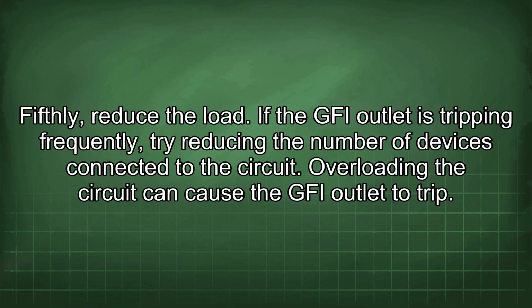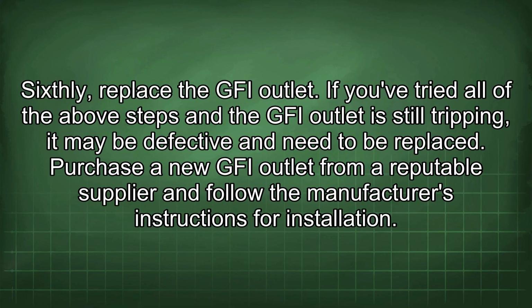Fifthly, reduce the load. If the GFI outlet is tripping frequently, try reducing the number of devices connected to the circuit. Overloading the circuit can cause the GFI outlet to trip. Sixthly, replace the GFI outlet. If you've tried all of the above steps and the GFI outlet is still tripping, it may be defective and need to be replaced. Purchase a new GFI outlet from a reputable supplier and follow the manufacturer's instructions for installation.